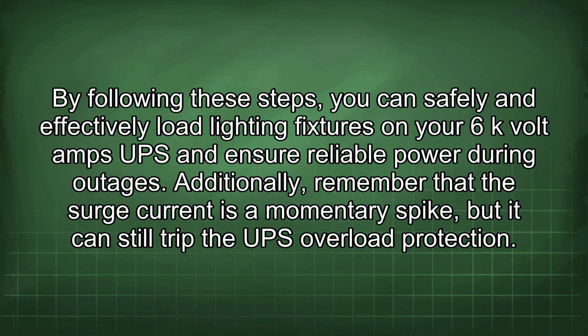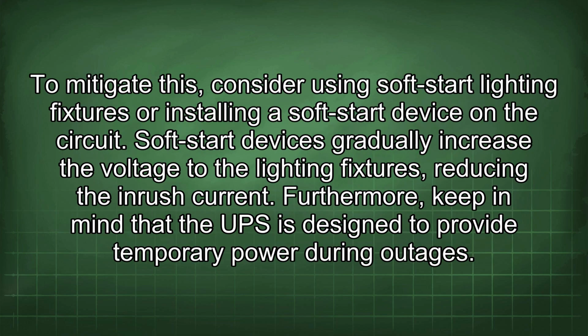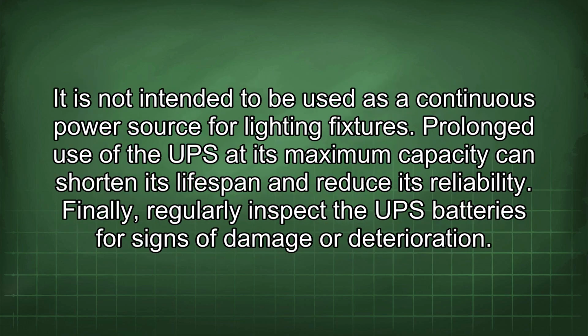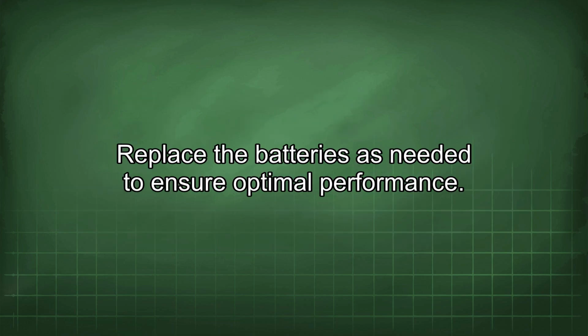Additionally, remember that the surge current is a momentary spike, but it can still trip the UPS overload protection. To mitigate this, consider using soft start lighting fixtures or installing a soft start device on the circuit. Soft start devices gradually increase the voltage to the lighting fixtures, reducing the inrush current. Furthermore, keep in mind that the UPS is designed to provide temporary power during outages. It is not intended to be used as a continuous power source for lighting fixtures. Prolonged use of the UPS at its maximum capacity can shorten its lifespan and reduce its reliability. Finally, regularly inspect the UPS batteries for signs of damage or deterioration. Replace the batteries as needed to ensure optimal performance.